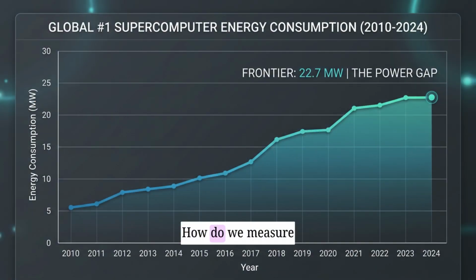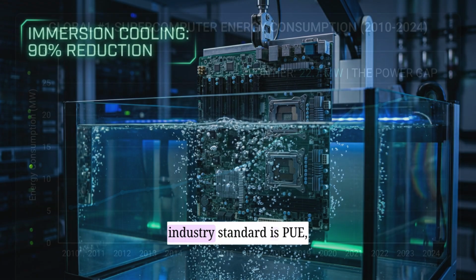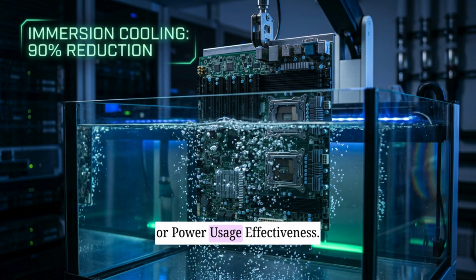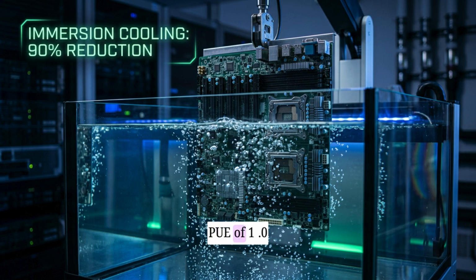The statistics show that we are reaching a point where the cost of electricity is beginning to outpace the cost of the hardware itself. How do we measure if a data center is actually efficient? The industry standard is PUE, or Power Usage Effectiveness. A PUE of 1.0 would mean every watt of power goes directly into computing. Anything above that is overhead, mostly cooling. While the average data center sits around 1.5, the world's most advanced HPC sites are pushing down toward 1.03.